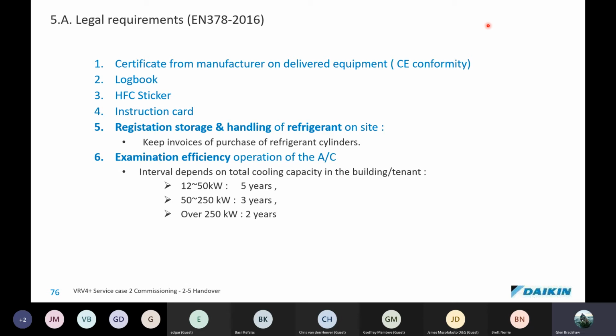Examination of the efficiency of the operation of the unit. Okay. The interval depends on the total cooling capacity, and it's recommended for 12 to 50 kilowatts every 5 years, 50 to 250 kilowatts every 3 years, and over 250 kilowatts every 2 years. Now, going back to what I spoke about earlier on, Daikin can, if you want, you can request a quotation from us to come out to a site, to couple up a service checker, to run the system through operation. Hopefully we can do heating and cooling depending on the outdoor conditions. And then we can give you a service report on that.